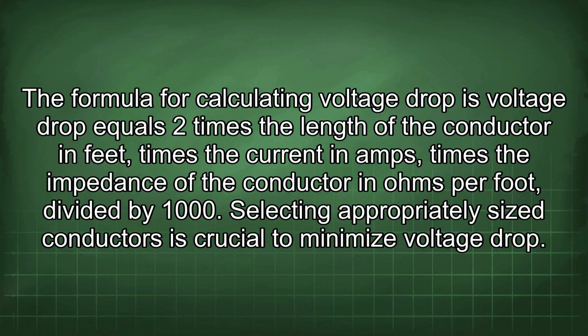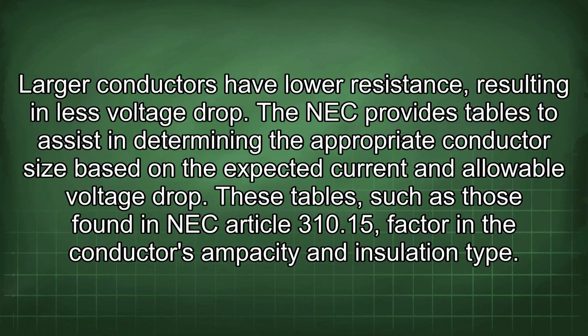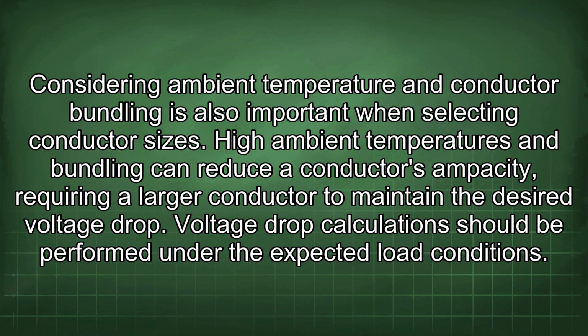Selecting appropriately sized conductors is crucial to minimize voltage drop. Larger conductors have lower resistance, resulting in less voltage drop. The NEC provides tables to assist in determining the appropriate conductor size based on the expected current and allowable voltage drop. These tables, such as those found in NEC Article 310.15, factor in the conductor's ampacity and insulation type. Considering ambient temperature and conductor bundling is also important when selecting conductor sizes. High ambient temperatures and bundling can reduce a conductor's ampacity, requiring a larger conductor to maintain the desired voltage drop. Voltage drop calculation should be performed under the expected load conditions.